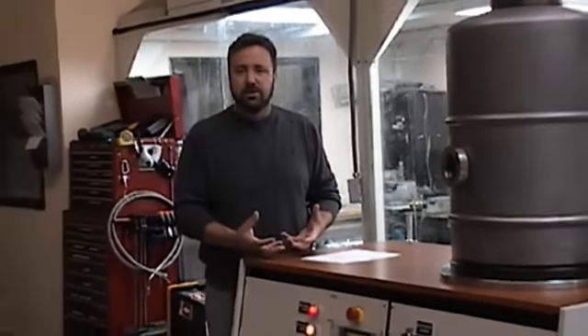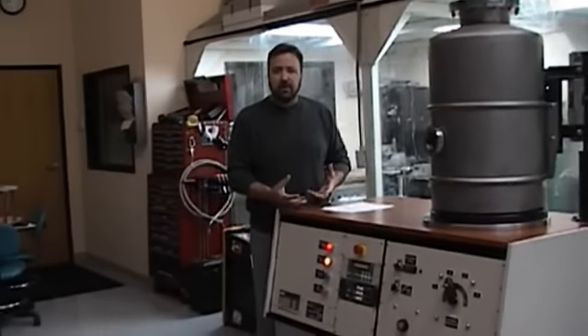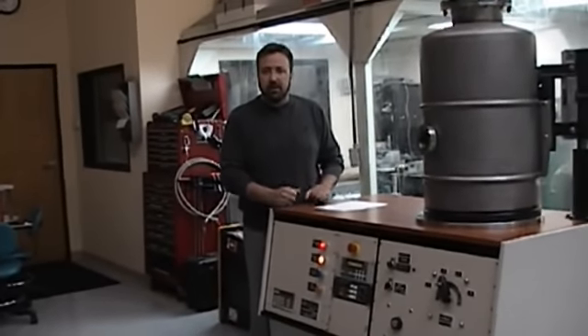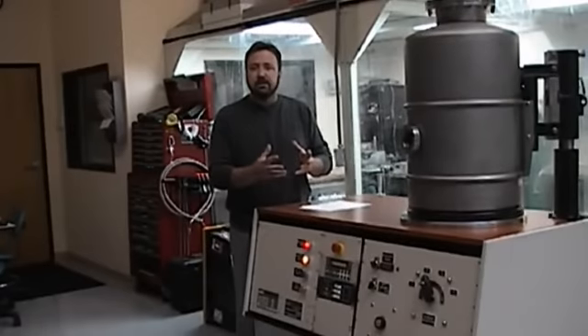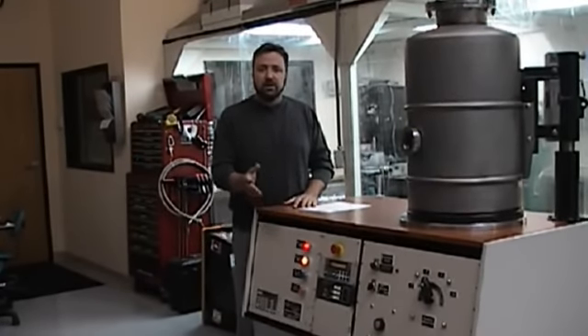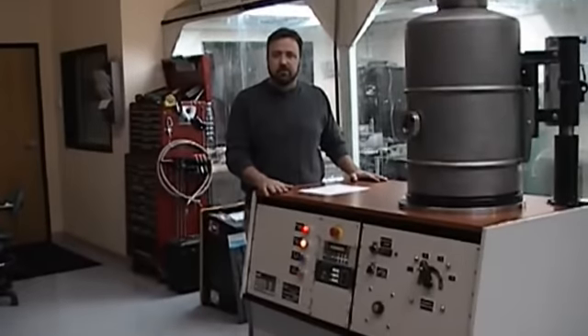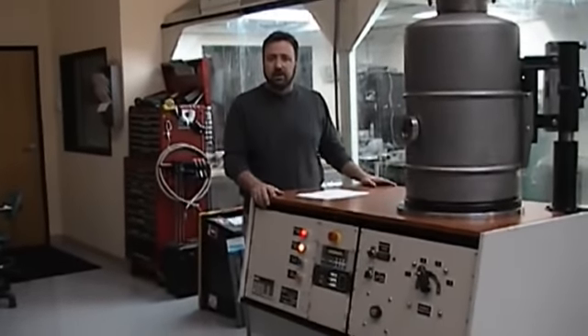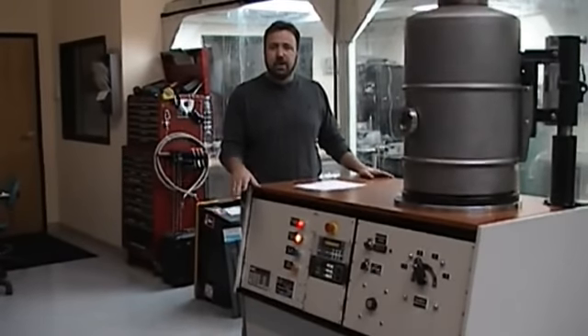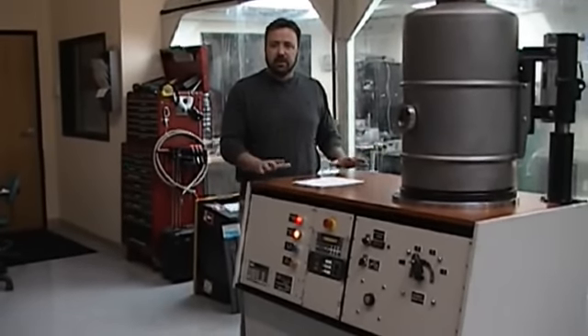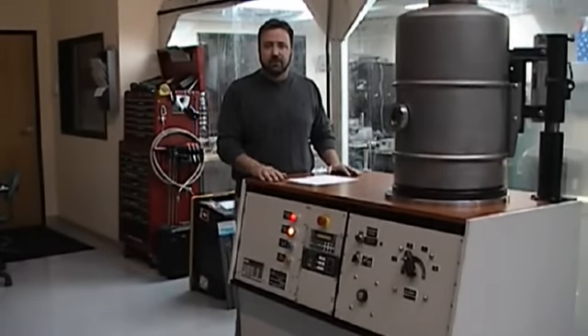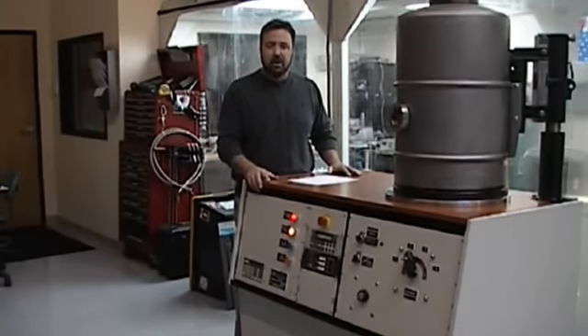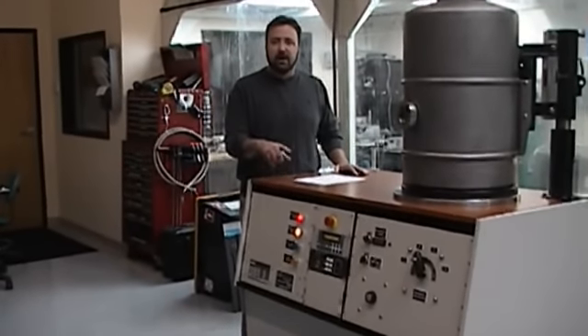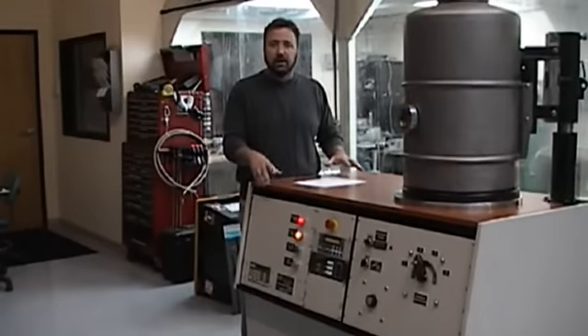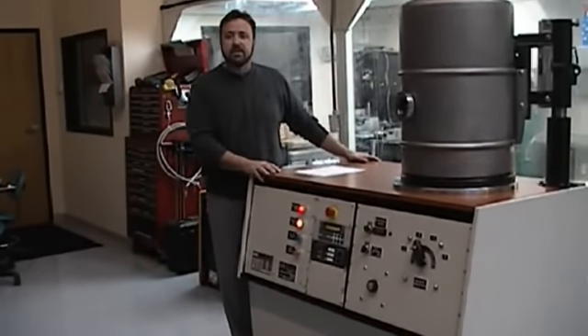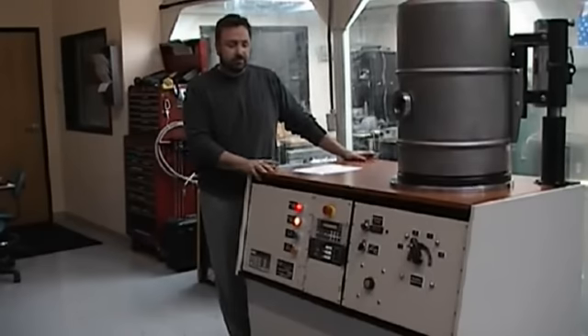Regenerating it basically dries the charcoal, makes the pump more efficient, dispels all the gases in there that need to be dispelled, and it regenerates it back to the point where you can bring it home. So if you're going to shut down the cryo pump system for, say, a long weekend or a week and you're not going to use it, run a regen, have it ready to go, leave it in that status, shut it off. It'll stay under vacuum, it'll stay dry, then when you're ready to go, the regen cycle that it goes through before you start up really quickly, and as you hear it, that's the way it should operate.